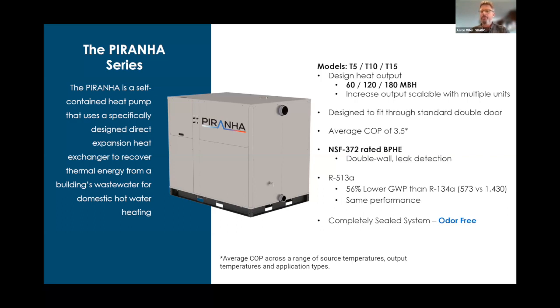We're using wastewater, it's nasty stuff, it's toxic. So we use an NSF 372 rated brazed plate heat exchanger, which means complete separation between the wastewater side and the potable water side. There's never any cross-contamination, so it's completely safe to use inside a building for potable hot water.